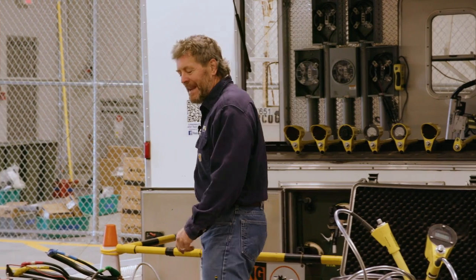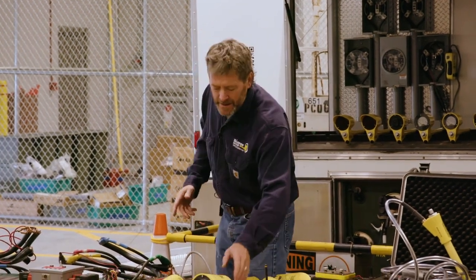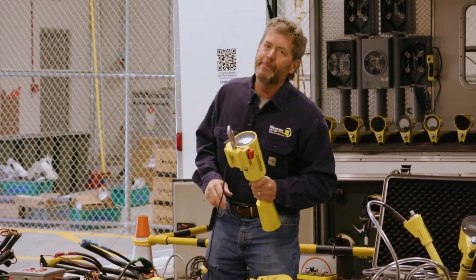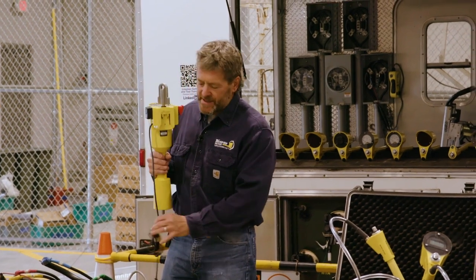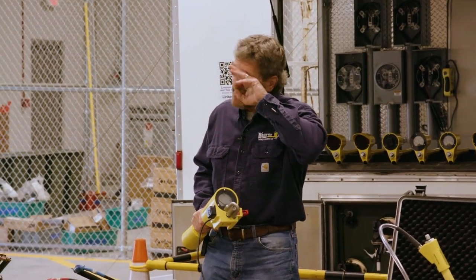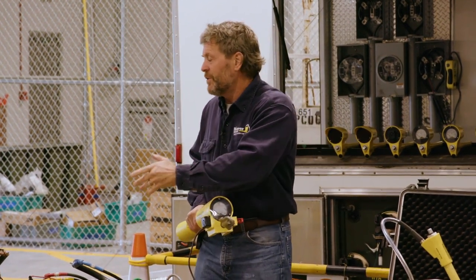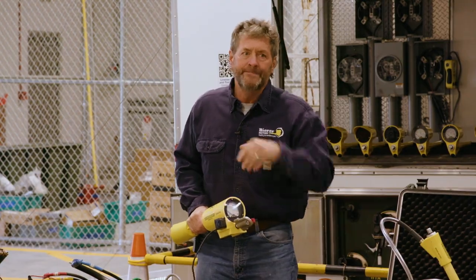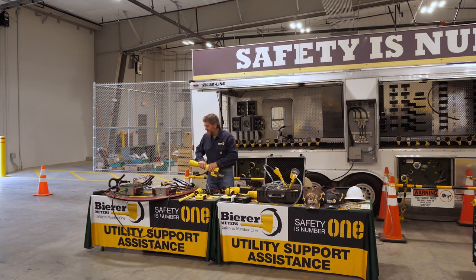They liked that. Anyways, real quick, the high potter. This is a high pot tool, and you can use this quickly on new construction or existing lines to verify if the span between transformers is good or bad. You simply use an 18 volt Milwaukee or Makita, turn it on.